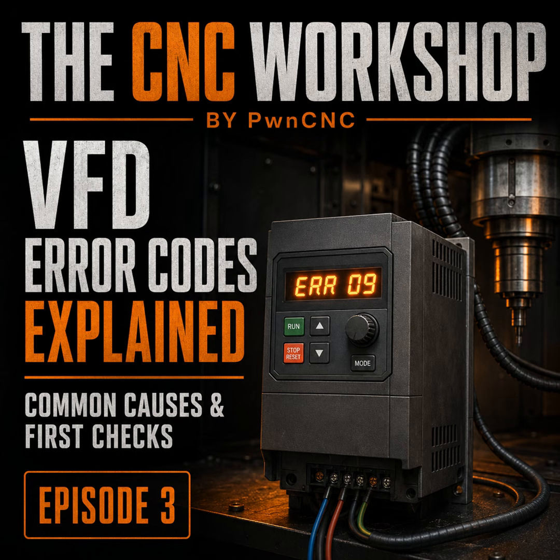All right, back to our collection of angry little error codes. Let's move to ERR31, which may also appear as 031. The article calls this a current detection fault. How is that different from ERR09? ERR09 generally points toward a sustained operating overload. ERR31 is more closely associated with the VFD's current detection circuitry or related electrical conditions. It can indicate an internal VFD problem, although cable damage, grounding problems, loose or overheated connections, electrical noise, or a problem inside the spindle can also be involved.